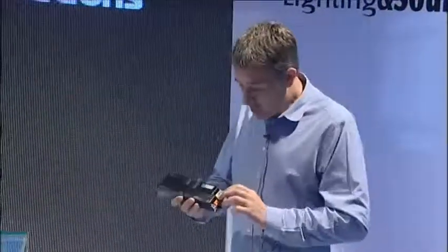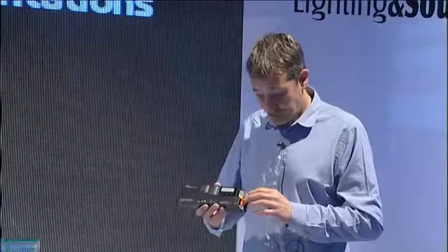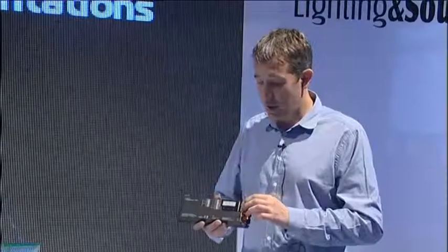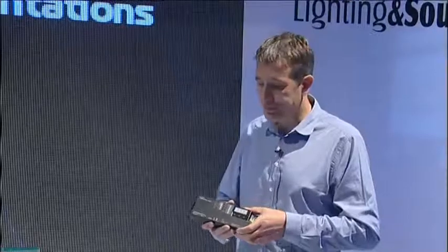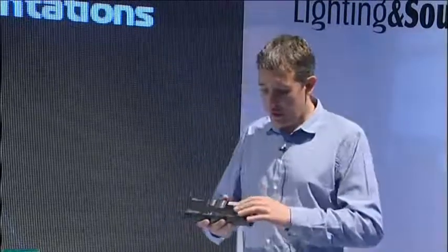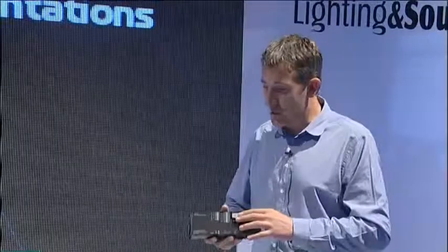You can download up to 19 programs into the driver, and from those 19 you have complete choice of what those programs do. So if it's a small installation and you don't want to use DMX, the driver will run its own show. Obviously, with a complex user interface and lots of buttons, people get trigger happy, so there are 2 levels of software lock, where you can leave it open, close it completely, or just leave access to certain key features, particularly DMX start addresses.